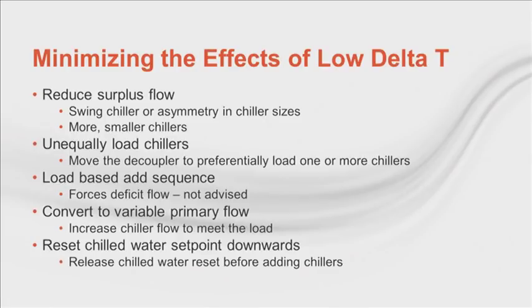This reduces the flow in the secondary loop and delays the need for adding a chiller. Most of the time, the chiller has the ability to make the water colder. It will come back at the same temperature or warmer than it did before, depending on the style of coils in your building. Some or all of the lost chiller capacity is restored.